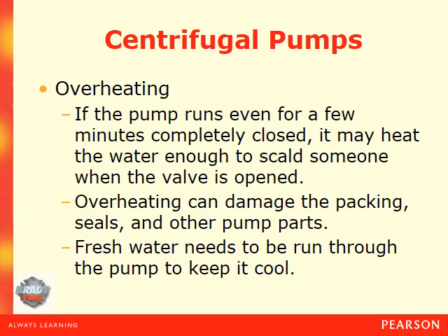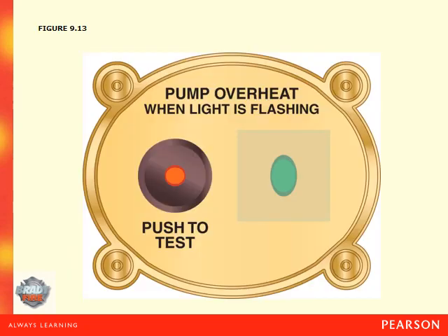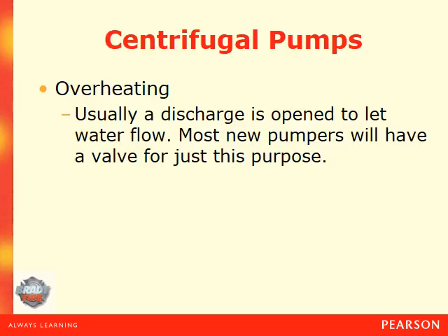Overheating: if the pump runs even for a few minutes completely closed, it may heat the water enough to scald someone when the valve is opened. Overheating can damage the packing seals and other pump parts. Fresh water needs to be run through the pump to keep it cool at all times. Usually a discharge is open to let water flow, and most new pumps will have a valve for just this purpose.